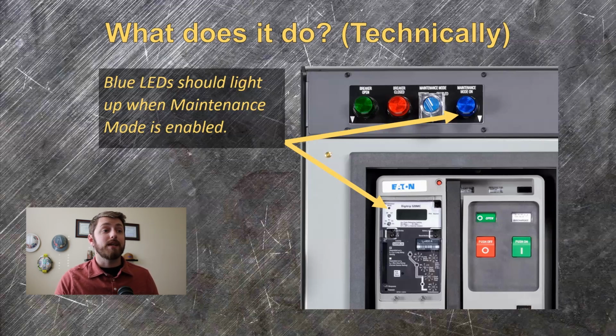Some trip units will make it easy and have a blue LED right on the front, like on this Eaton Digitrip 520MC, but I know on some Square D breakers, the MicroLogic 6.0 trip units will only show it as a settings change that's nested really far down into the menus. Once enabled, they typically lower the instantaneous trip pickup. This can either be displayed as simply lowering the setting or by activating some other mode in the trip unit.